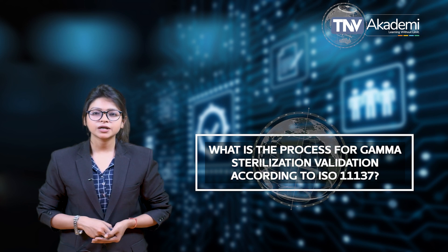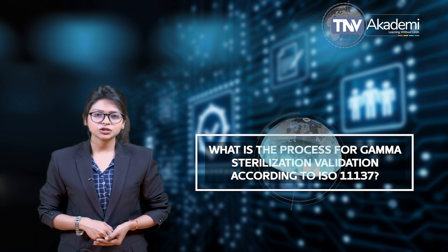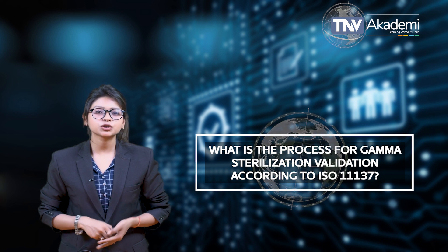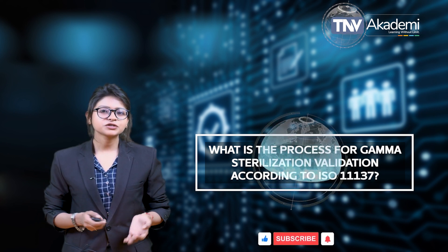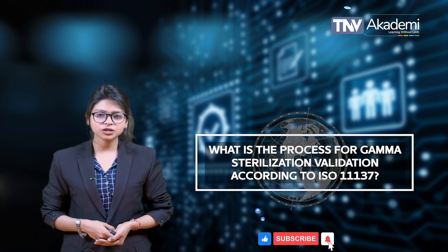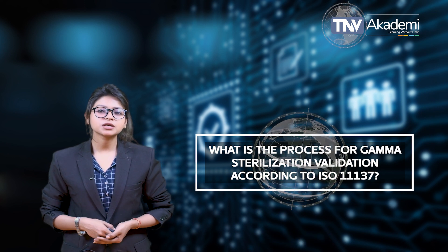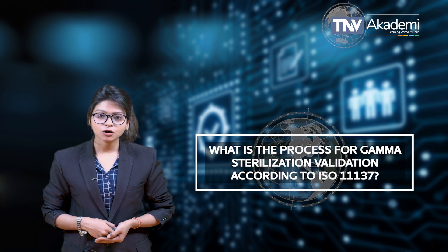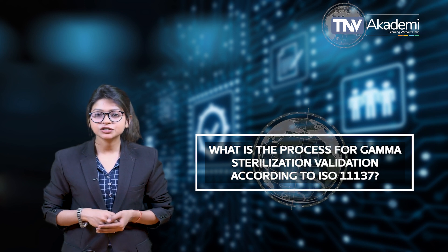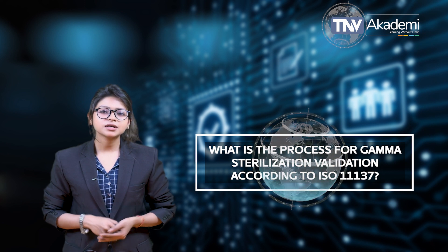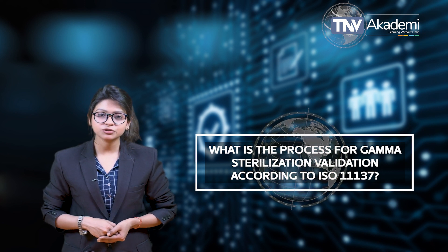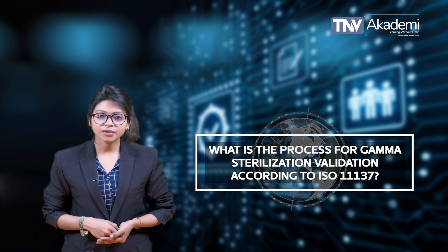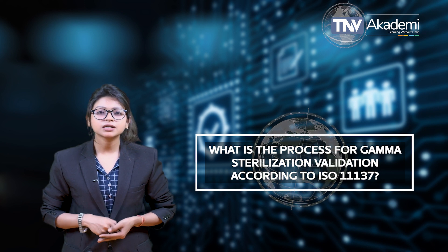The gamma sterilization validation process outlined in ISO 11137 is meant to ensure two critical outcomes. The first is that the desired Sterilization Assurance Level (SAL) is met using a minimum dose of radiation. The most commonly specified SAL is 10⁻⁶, or one potentially unsterilized device per million. The second is that product functionality is not compromised by exceeding a maximum dose of radiation.